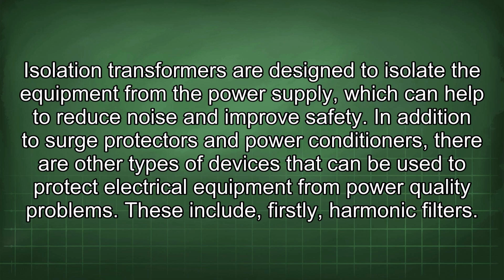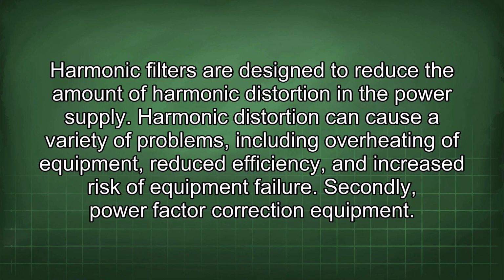In addition to surge protectors and power conditioners, there are other types of devices that can be used to protect electrical equipment from power quality problems. These include, firstly, harmonic filters. Harmonic filters are designed to reduce the amount of harmonic distortion in the power supply. Harmonic distortion can cause a variety of problems, including overheating of equipment, reduced efficiency, and increased risk of equipment failure.